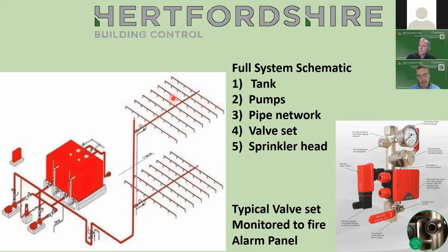If you haven't balanced your radiators, if all your valves are open and your central heating kicks in, then this closest radiator will get hot really quick, and the radiator that's furthest away will warm up really slowly. So the idea is that you can put an orifice plate in here, which makes that hole slightly smaller. So it needs more pressure to get through to that sprinkler head and less to that, and obviously it balances it up a little bit better. That's your first port of call.